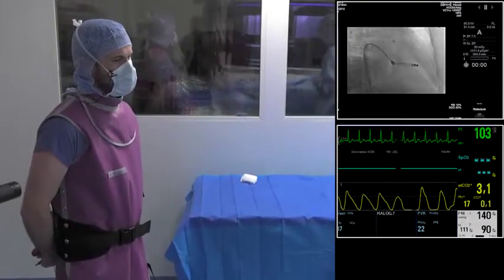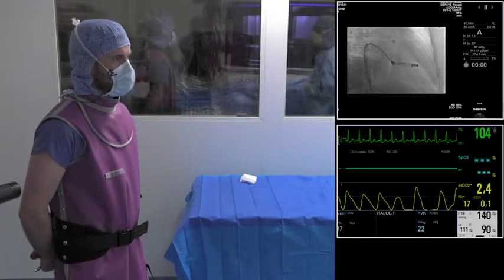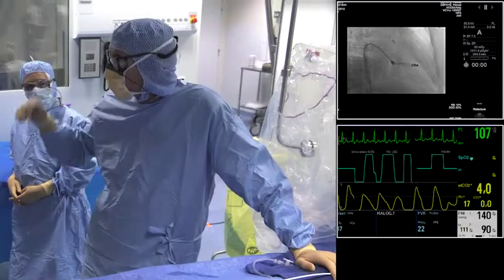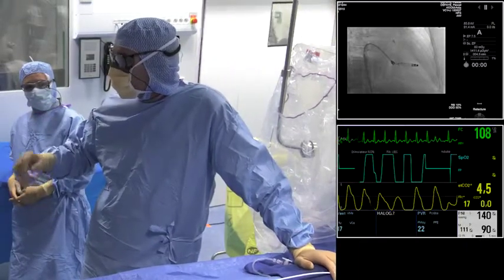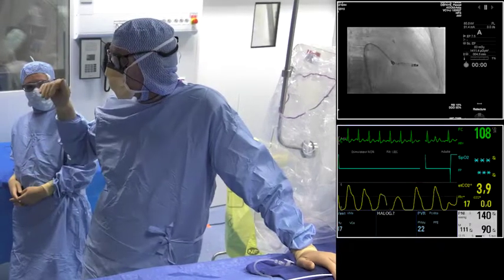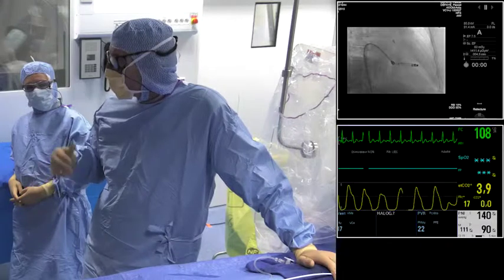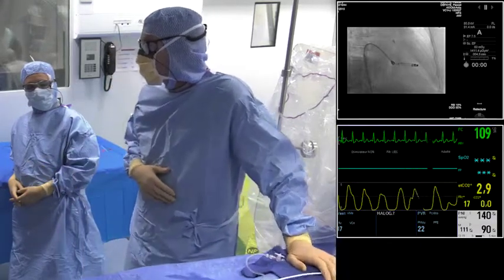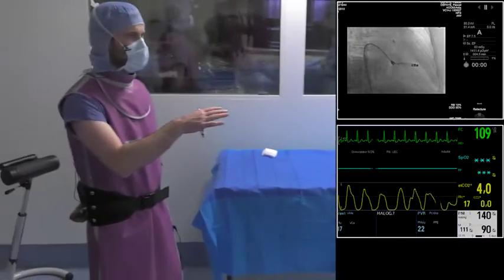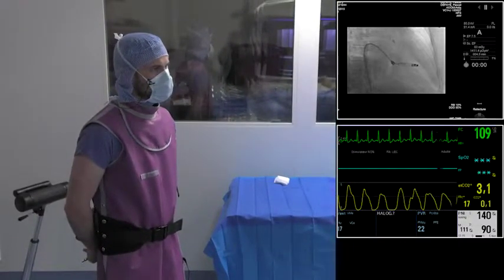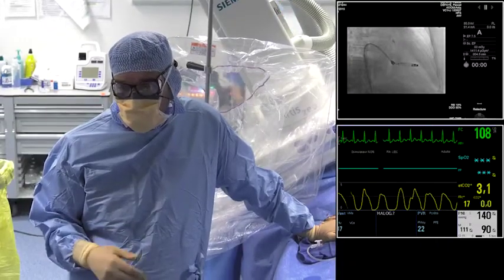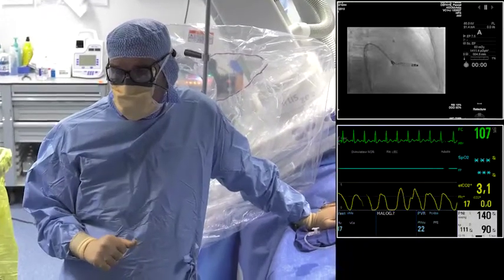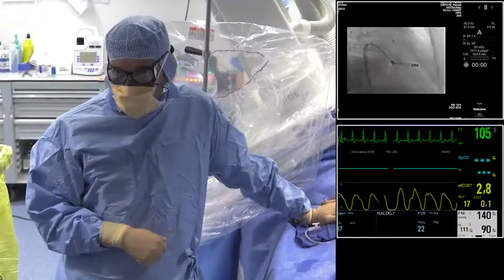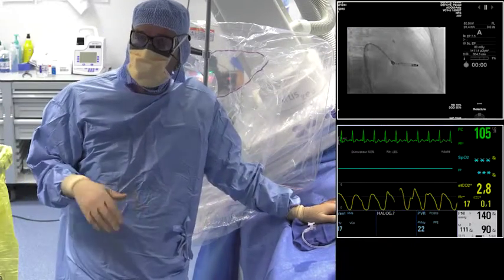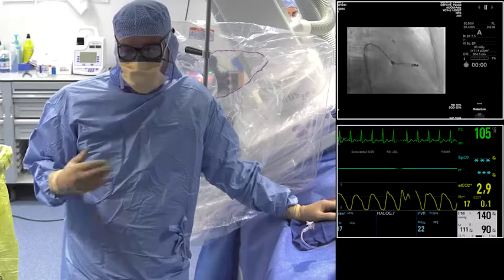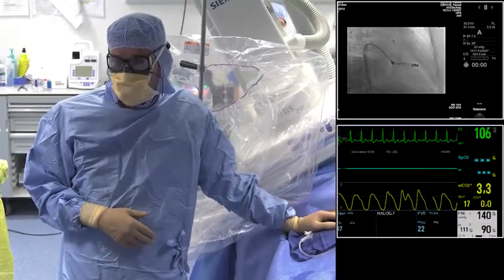Okay. What would be your advice for a good threshold in order to release your device? I think it's very important to have a trend. If there is a trend with a decrease of the threshold, if we begin at 3 and there is a decrease and we have at 5 minutes 2 volts, I think we are relatively sure that it's a good position and that we can release the device. So would you advise 2 volts or maybe 1.5 volts as a cutoff? 1.5 is better, but if we have 2 volts and there is a trend to a decrease and the position is okay, I think we can release the device. We have done a release sometimes at 2 volts and always an excellent threshold at 24 hours.